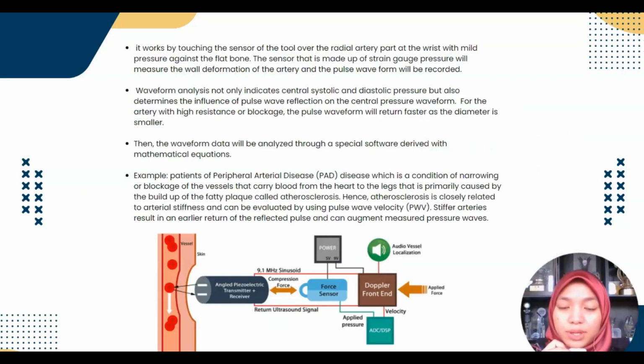For the working principle of the radial applanation tonometry, it works by touching the sensor of the tool over the radial artery part at the wrist with mild pressure against the flat bone. The sensor, made up of a strain gauge pressure, will measure the wall deformation of the artery, and the pulse waveform will be recorded. Waveform analysis not only indicates central systolic and diastolic pressure, but also determines the influence of pulse wave reflection on the central pressure waveform.